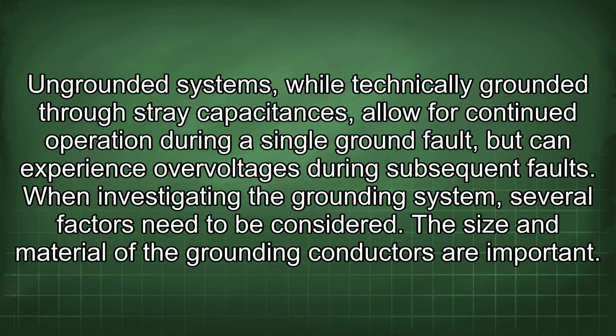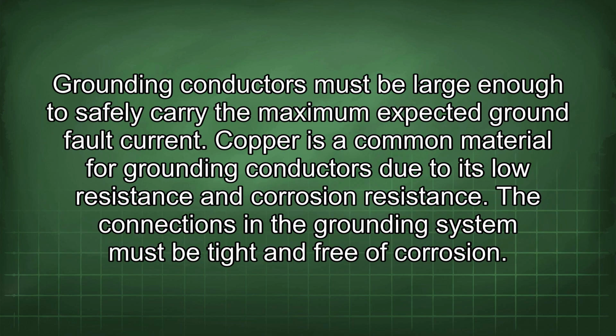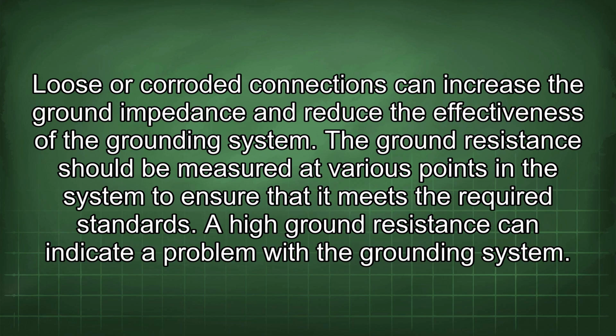The size and material of the grounding conductors are important. Grounding conductors must be large enough to safely carry the maximum expected ground fault current. Copper is a common material for grounding conductors due to its low resistance and corrosion resistance. The connections in the grounding system must be tight and free of corrosion. Loose or corroded connections can increase the ground impedance and reduce the effectiveness of the grounding system. The ground resistance should be measured at various points in the system to ensure that it meets the required standards. A high ground resistance can indicate a problem with the grounding system.